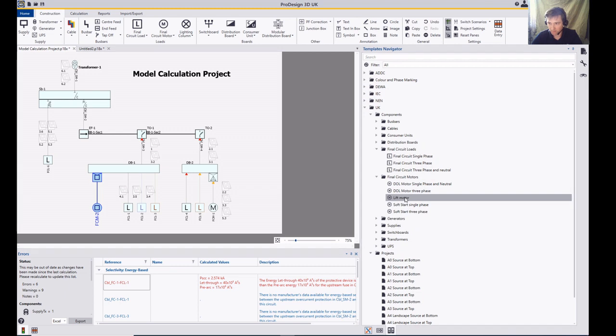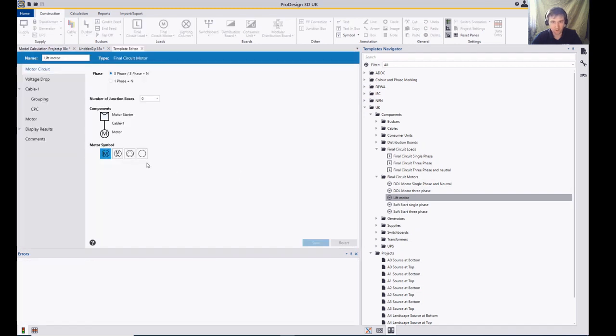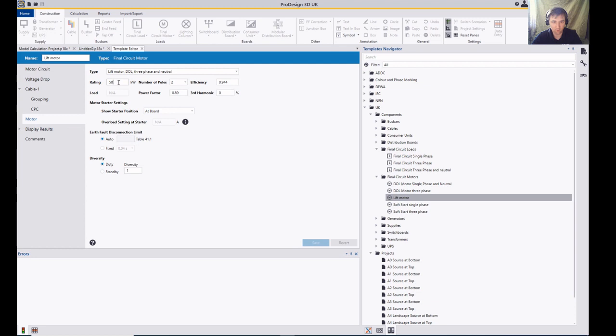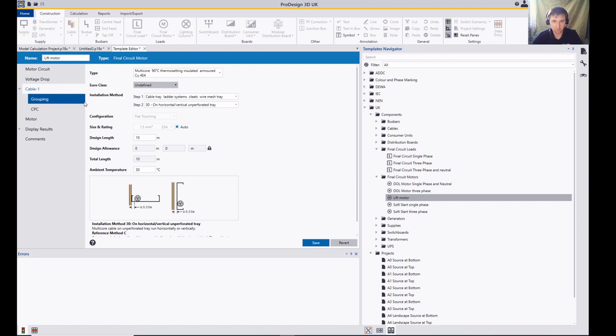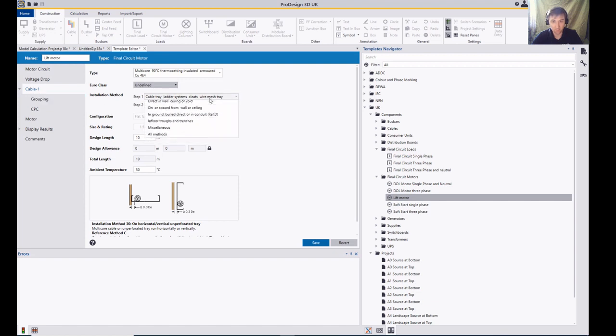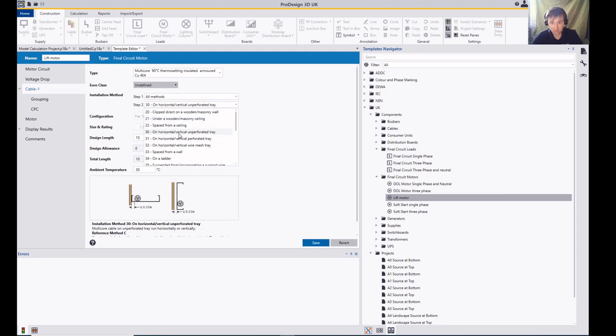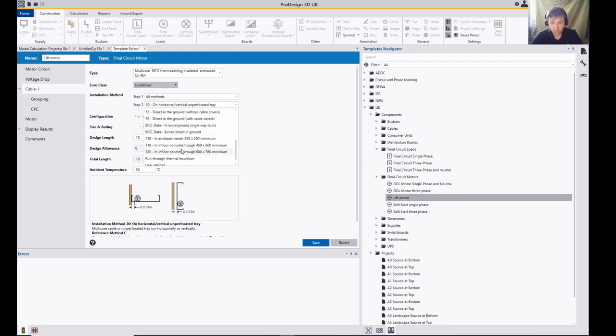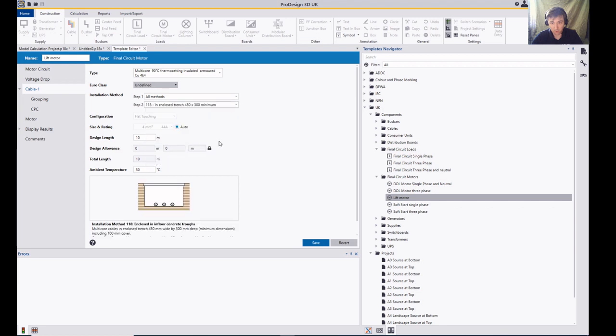But say for some reason I want to edit that — I can come in here, go to the motor, and say I don't want it to be 50, I want it to be 45. And as for the cable, I don't want it on perforated tray, I don't want it on ladder — I want to use all methods and I want to say it's generally going to be installation method 118.